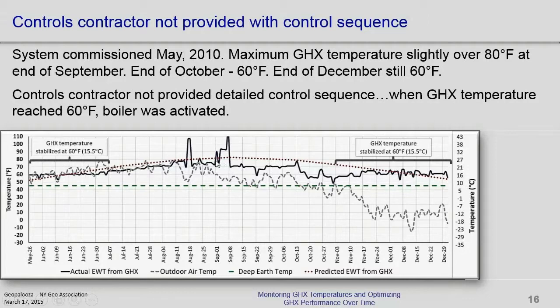And then gradually dropped a little bit and leveled out at about 60 degrees Fahrenheit. These are just a couple of anomalies in the system for some reason in the first season. But basically, one of the problems was that the controls contractor that was hired by the mechanical engineers that designed the building system had told them, this is a heat pump system. You know how those work, just put the controls in.